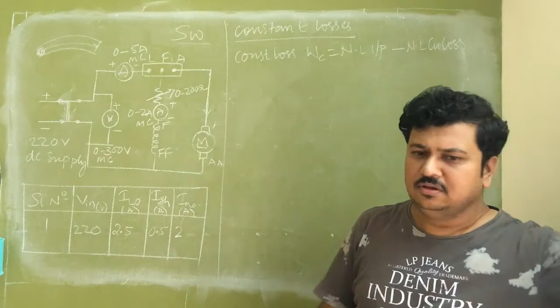Therefore, it is loss. Now, whatever the loss I am getting at no load is the combination of constant loss and a small amount of variable loss. Why a small amount of variable loss? The current is very small. 2.5 amperes is very small when compared to 13.3 amperes, hardly around 20% you can consider. Therefore, out of these total losses, which are constant loss plus variable loss, the loss which I am getting from the input is conduction loss plus magnetic loss plus mechanical loss. But I know what the constant losses are.